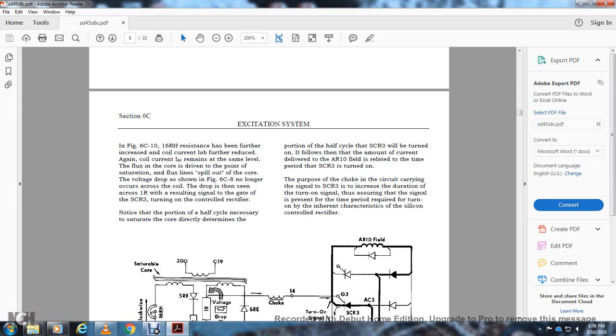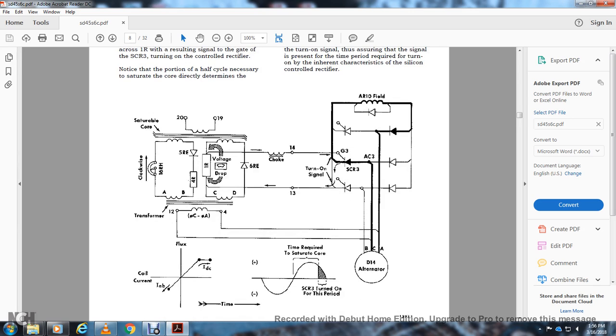Note that the portion of the half cycle in which the saturating current flows determines how much of the half cycle silicon rectifier 3 will turn on. It will flow for the amount of current developed. The AR10 alternator field winding is related to the time and the period that the silicon rectifier is turned on. The purpose of the choke in this circuit is to carry on the signal of the silicon rectifier, to improve the duration of the turn-on signal, ensuring that the signal is present for the time period required for turning on the inherent characteristic of the silicon controlled rectifier.